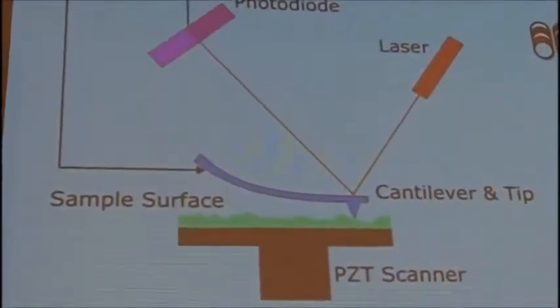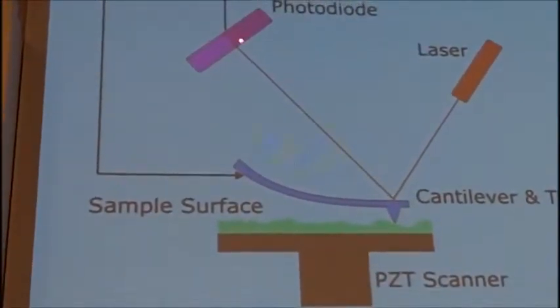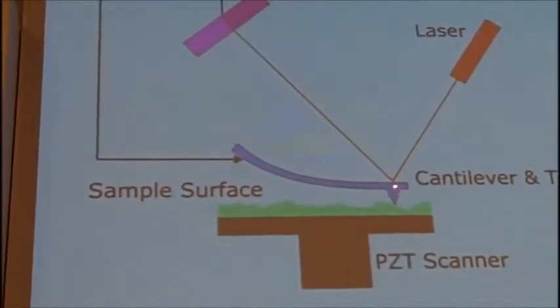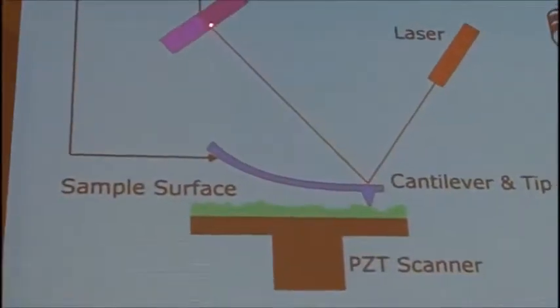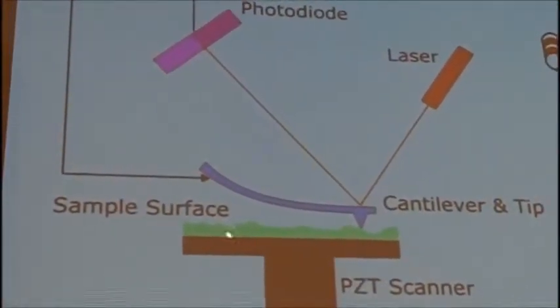It's a photosensitive detector, and this way we're always monitoring what's happening to the cantilever. When the cantilever is far away from the sample, nothing is happening—the laser will stay at the center of the detector. We align it in such a way that in the beginning the laser will stay in the center of the detector. When the tip is very close to the sample, the cantilever will start deflecting and this laser, instead of hitting the middle, will hit a bit above or a bit below, depending on the topography of the sample. So that's our feedback to know what's going on there.